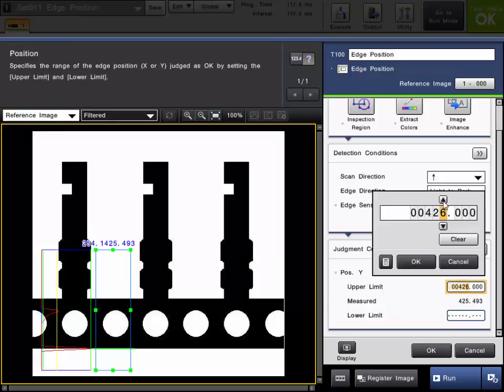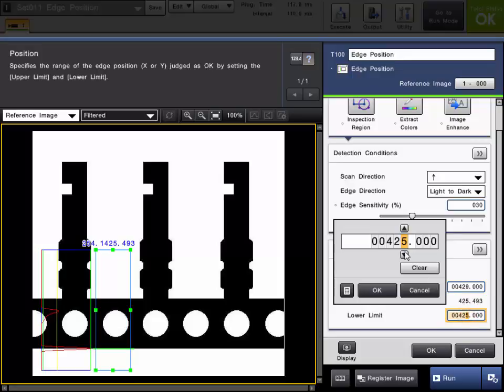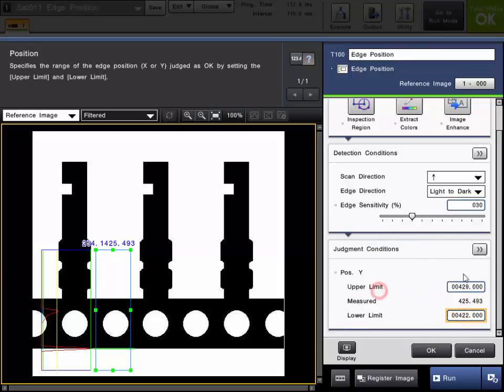If we want this to fail if this gets too far out of position, we will set an upper limit of about 429 in this example, and maybe a lower limit of 422. So you would set that limit according to the application.